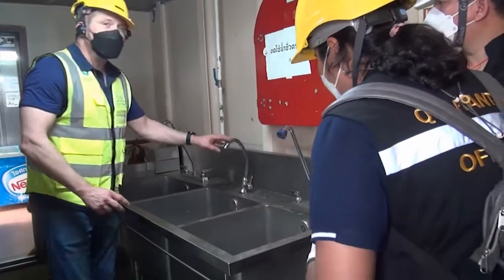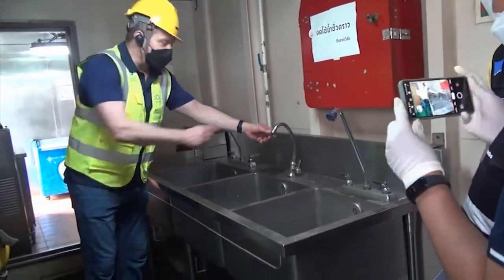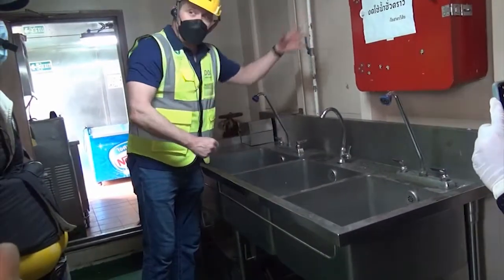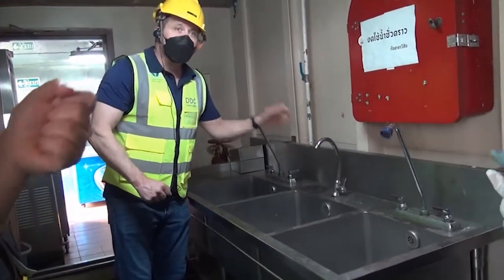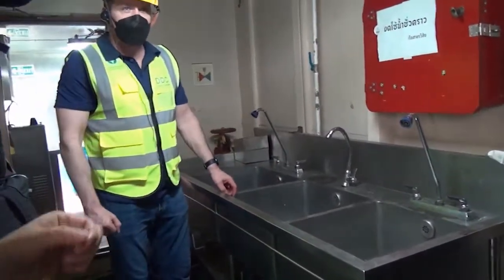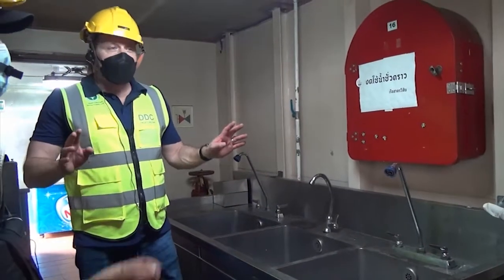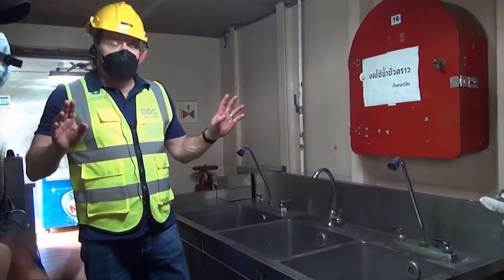And I asked you about the backflow prevention. When it would need one is if there was a hose with a spray one. Now you need a backflow prevention device because that spray one could get dropped in here accidentally. And now you have a direct connection. Thank you for your attention, guys.